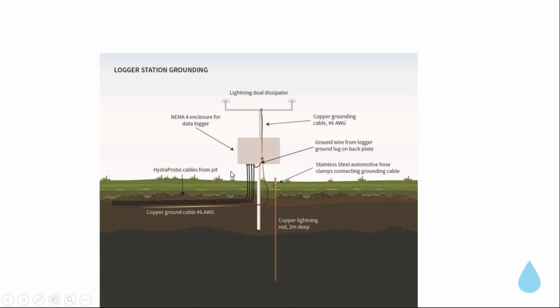It's connected in with this cable, which is again another grounding rod going 2 meters deep at your logger station. Most data loggers have a grounding lug, so you could take the lug and put a ground wire on it, then bring that out of the enclosure and connect it in with the grounding system of the whole station.